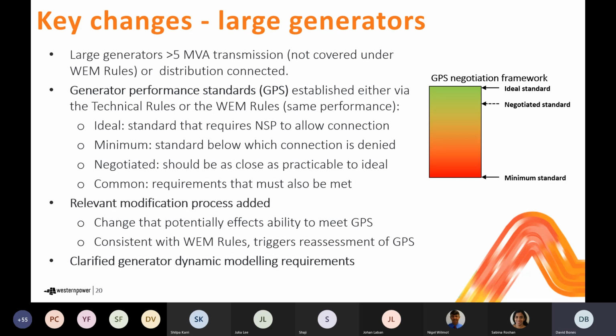So what are the generator performance standards? If you think about it, the generator performance standard framework describes a negotiation range. So for each one of 11 technical requirements, there's a need to negotiate what's called a generator performance standard, which defines the agreed level of performance that the generating system needs to achieve. Now that agreed level of performance is what we call a negotiated standard, and it needs to be set so that it is between what's termed an ideal standard and a minimum standard.